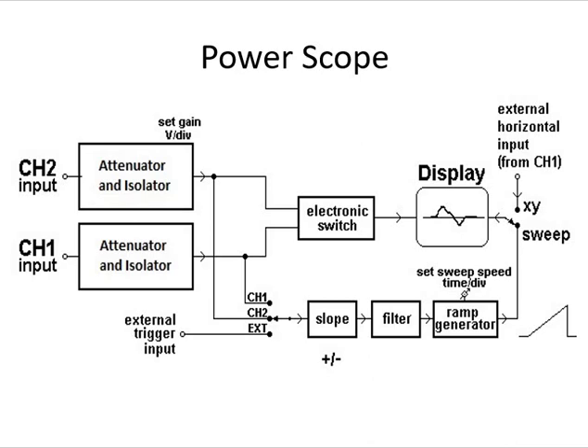A power scope is an oscilloscope designed to measure and display voltages and waveforms in both low power and high power circuits simultaneously. That's why two inputs are used — channel 1 and channel 2. A power scope is a dual-trace oscilloscope, meaning it can display two waveforms simultaneously. It incorporates special safety features such as a fully grounded front panel and controls to minimize operator shock hazard, and can withstand transient voltages up to 2 kV at all vertical amplifier inputs.